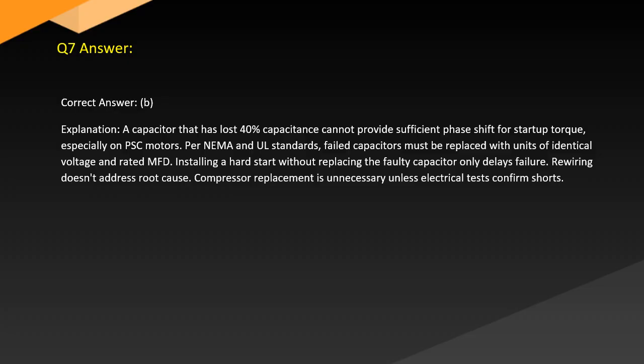Answer. Correct answer: B. Explanation. A capacitor that has lost 40% capacitance cannot provide sufficient phase shift for startup torque, especially on PSC motors. Per NEMA and UL standards, failed capacitors must be replaced with units of identical voltage and rated MFD. Installing a hard start without replacing the faulty capacitor only delays failure. Rewiring doesn't address the root cause. Compressor replacement is unnecessary unless electrical tests confirm shorts.